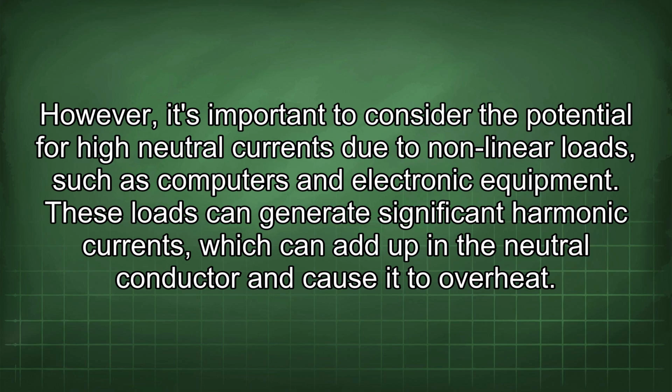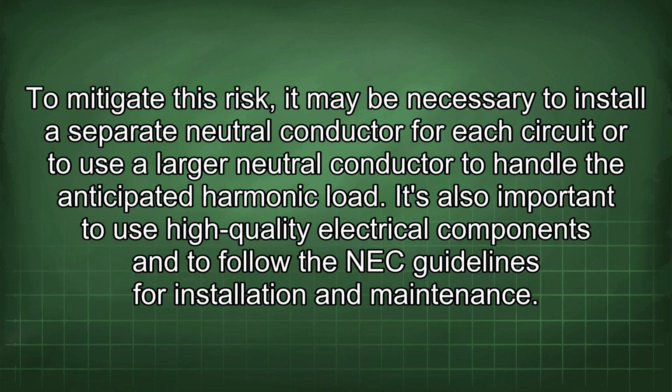These loads can generate significant harmonic currents, which can add up in the neutral conductor and cause it to overheat. To mitigate this risk, it may be necessary to install a separate neutral conductor for each circuit or to use a larger neutral conductor to handle the anticipated harmonic load.